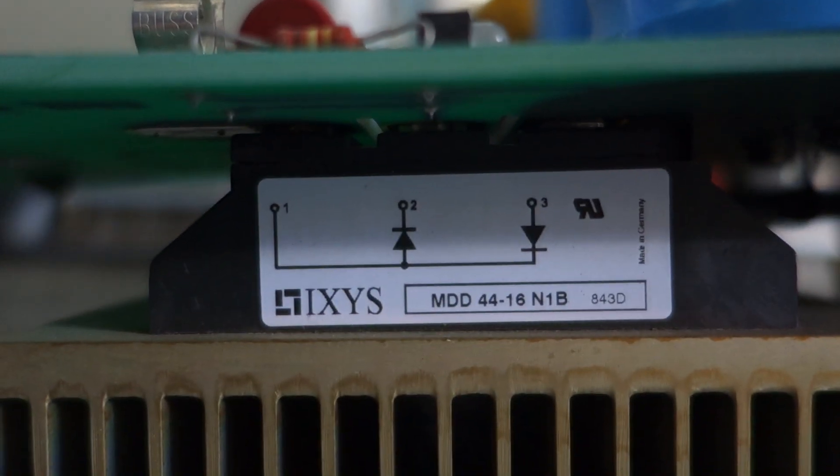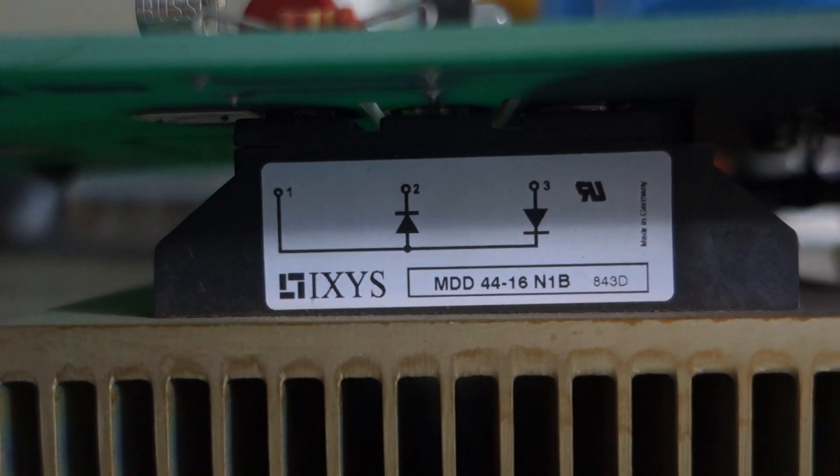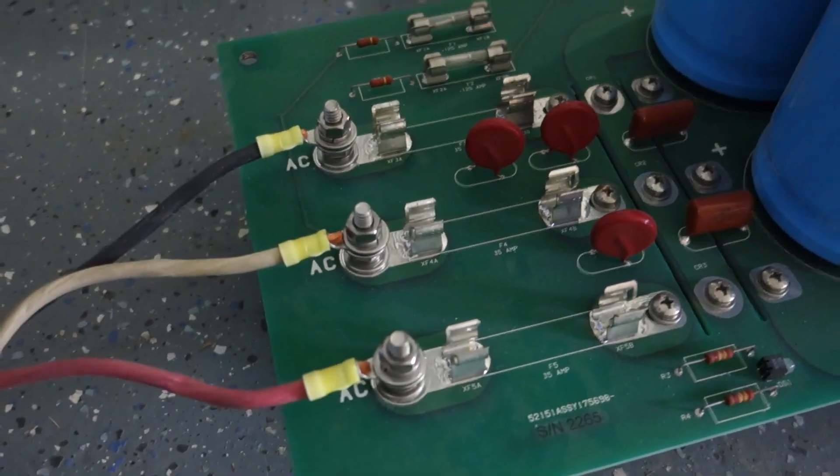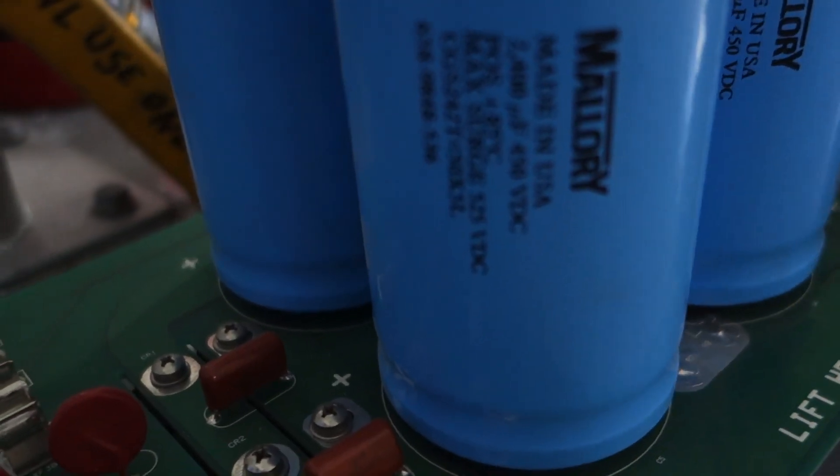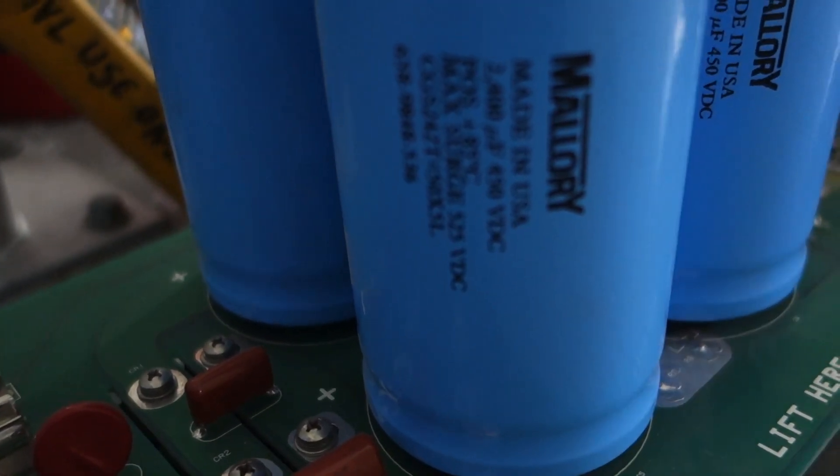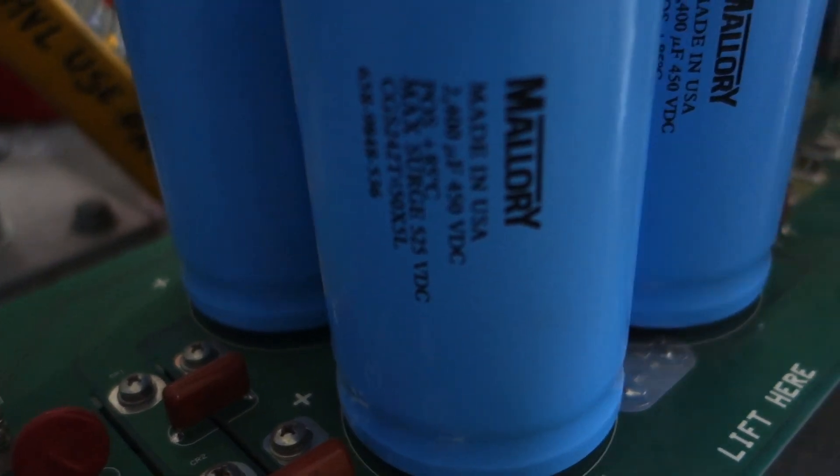So that takes 480 three-phase and turns it into nice filtered DC. We know it's filtered because there's the filter caps, big ones. Those are thumper caps. Well, close—those are 2400 microfarad at 450 volts, and they're an inferior brand.